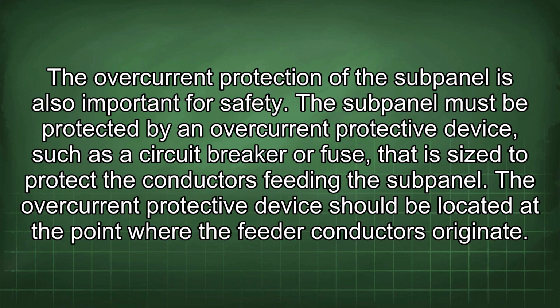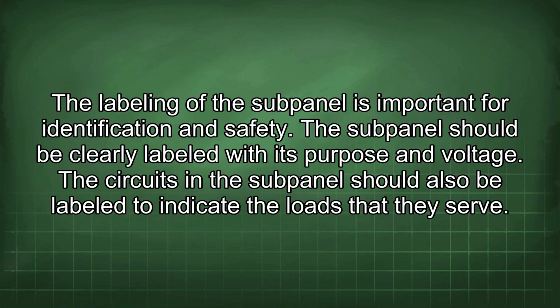The subpanel must be protected by an overcurrent protective device such as a circuit breaker or fuse that is sized to protect the conductors feeding the subpanel. The overcurrent protective device should be located at the point where the feeder conductors originate. The labeling of the subpanel is important for identification and safety. The subpanel should be clearly labeled with its purpose and voltage. The circuits in the subpanel should also be labeled to indicate the loads that they serve.